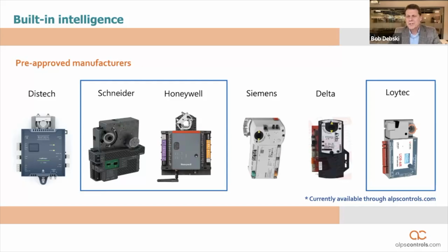So in order to achieve this level of control, controllers must be pre-tested to make sure they have the capability to perform this level of accuracy. That requires not just a fast-acting damper actuator, it requires a high turn-down, high-accuracy differential pressure sensor. It requires a high-accuracy damper position sensor. So not any controller is going to cut the mustard.